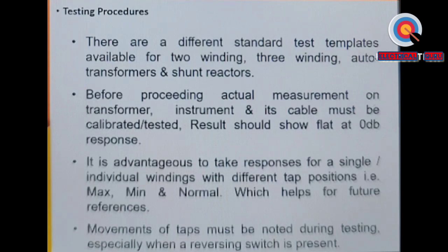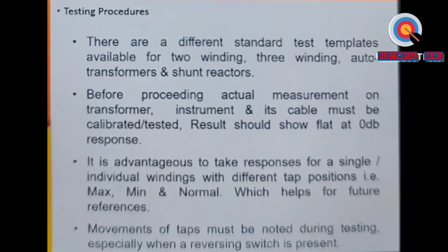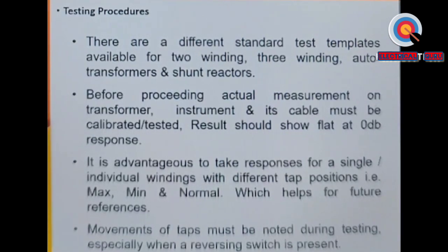Movements of tap must be noted during testing, especially when a reversing switch is present. Now, I'm sure you people are aware that when we have a tap changer, we achieve the change in turns ratio by changing the direction of current. So the tap winding is only one, but the same winding is used to add the turns or subtract the turns. That we achieve by reversing the current directions.